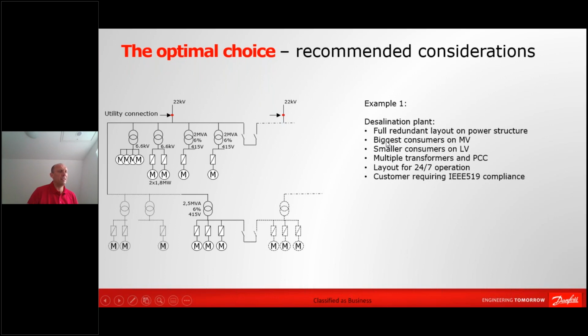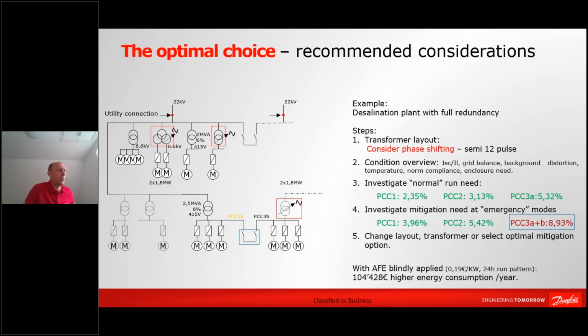Before you go there, there are actually a few things you could do to reduce harmonics already in your design phase. So the first thing to do is actually to consider if you can change some of the transformers. In this example here, I chose a different transformer. The one tapping of the transformer is now with a phase shifting. So you're doing a 12 pulse, and that means that the fifth order from the one drive is compensating the fifth order from the other drive simply because of this transformer setup.